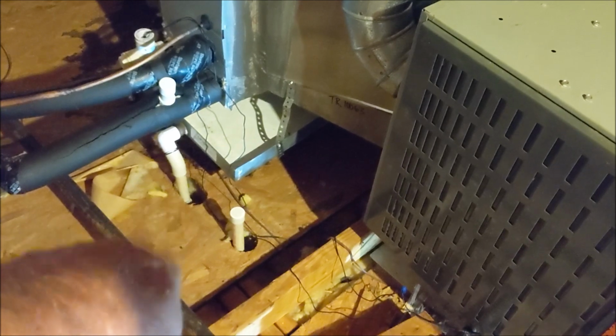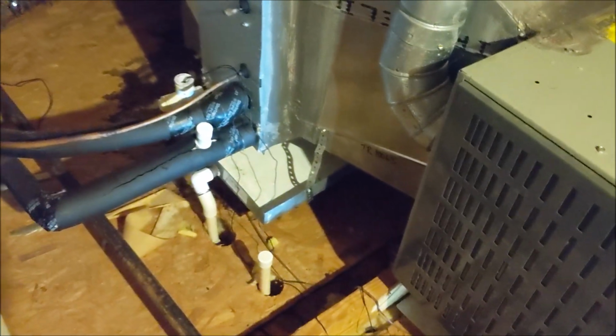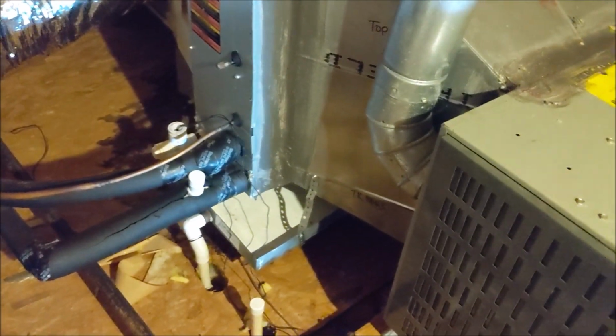So this is why some of that microbial growth here, we call it black stains, microbial growth, suspected mold growth, is forming. Guess what? Attic's hot, the cold air comes out, it hits that duct, it shoots back off, dust and condensation gets on it, thus creating the suspected mold growth. The emergency drain pan's good, got the line going to it, primary looks good, got a secondary float switch in place. This is a flat horizontal coil.